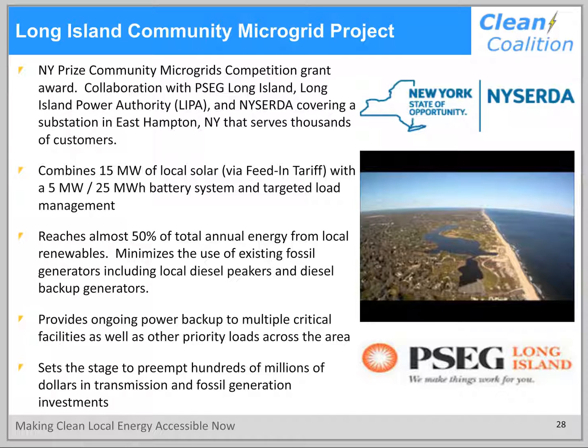For this project, we're combining 15 megawatts of local solar, procured through a feed-in tariff, with a 5 megawatt, 25 megawatt hour battery system, as well as some distributed energy storage at critical load sites, and targeted load management based on this DER portfolio. This system will reach almost 50% of the total annual energy from local renewables, and will minimize, or in some cases eliminate, the use of existing fossil fuel generators, which are basically diesel generators used to deal with summer peaks in the area.